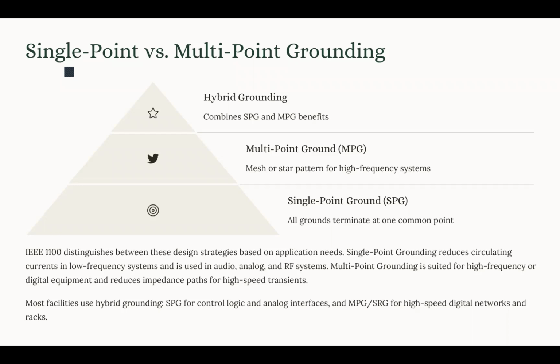Another strategy that we mentioned for grounding is multi-point grounding, where multiple ground connections are made at various points. It could be a mesh or star configuration, and it's normally implemented as the signal reference grid, the SRG, that we talked about. The application of this type of grounding is normally high-speed digital and broadband systems like data centers, broadcast, or high-frequency industrial automation systems. Multi-point grounding is sometimes preferred because it has a low high-frequency impedance. Multiple short parallel ground paths reduce inductive impedance, which provides fast transient dissipation.